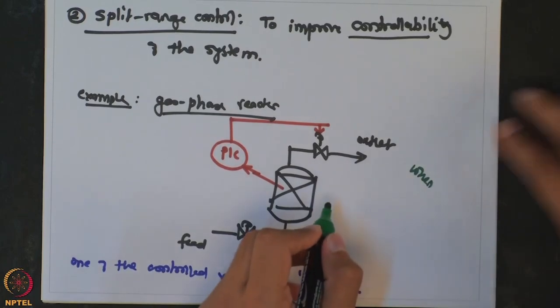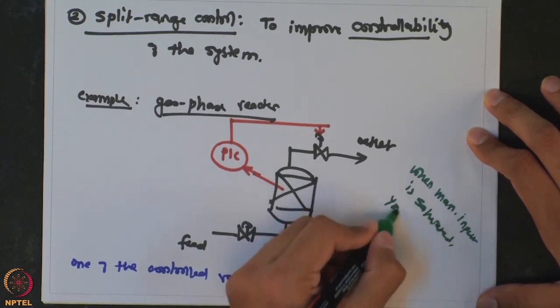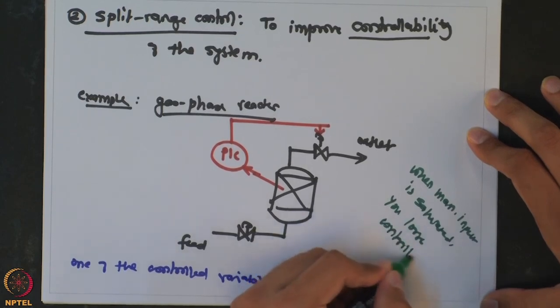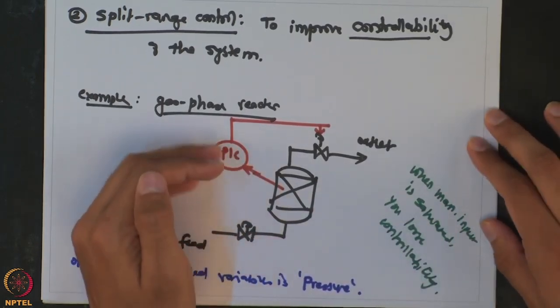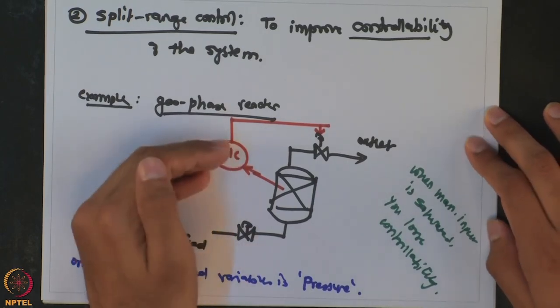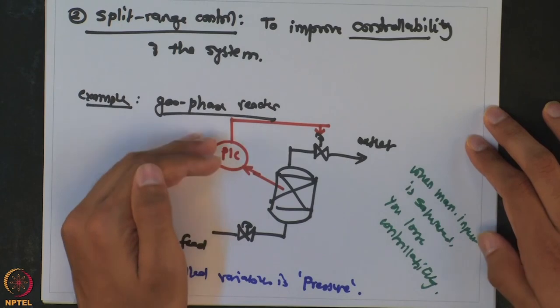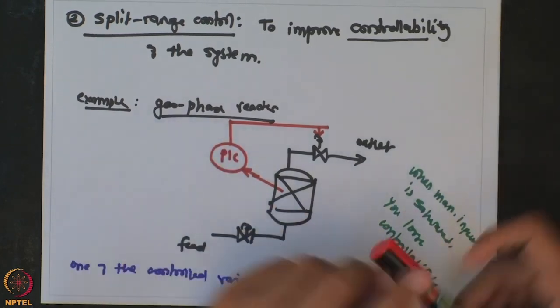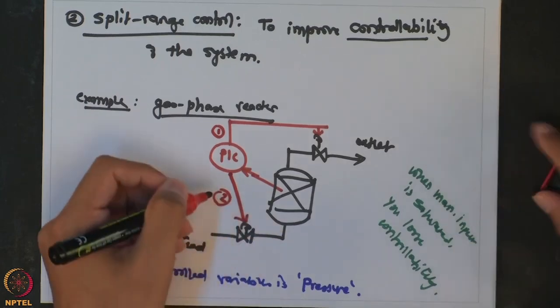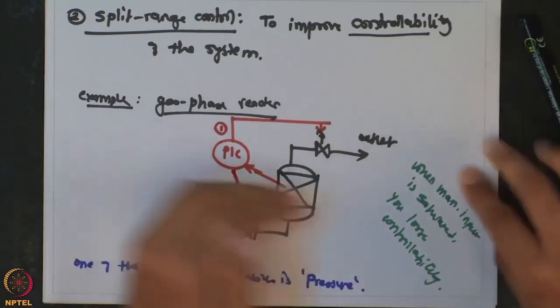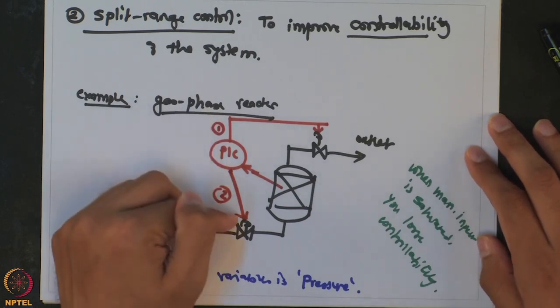When the manipulated input is saturated, the controller can no longer do anything to prevent pressure buildup. Another way to improve the response in such a situation is to cut down the feed — reducing reactant input reduces the reaction rate and vapor generation. So along with the outlet valve, if I also manipulate the inlet valve, as the outlet valve is saturated I can start cutting down the feed flow to ensure safety.